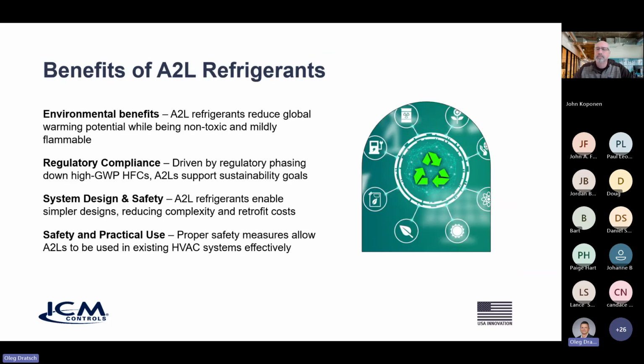Again, they're much better for the environment. We've driven down the GWP value of the hydrofluorocarbons, and just in general, A2L refrigerants enable simpler designs. Retrofit costs go down. It's a reduction in complexity. But with that, the trade-off being we need a proper way of mitigating any type of risk that may happen.